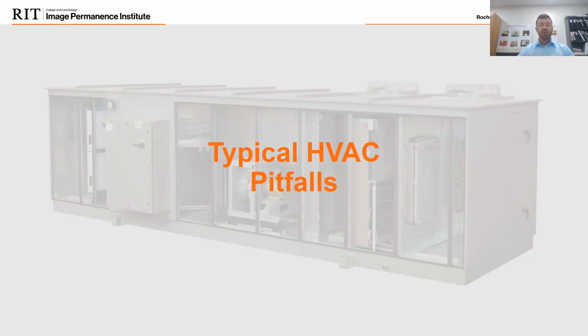If you imagine that subcool reheat, what we're thinking of is every time we're bringing that outside air in, we're having to dehumidify that. And if we're only dehumidifying at one unit, then we're only doing the major amount of work at one unit. That leaves the other units to really just do some sensible cooling as opposed to that dehumidification. So you pay more to run the main unit, but you're doing a lot less work cumulatively to the others by not having to dehumidify at those units. So yes, you use more, but a lot less.